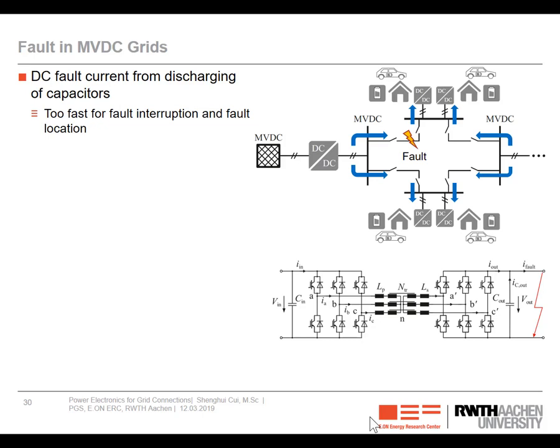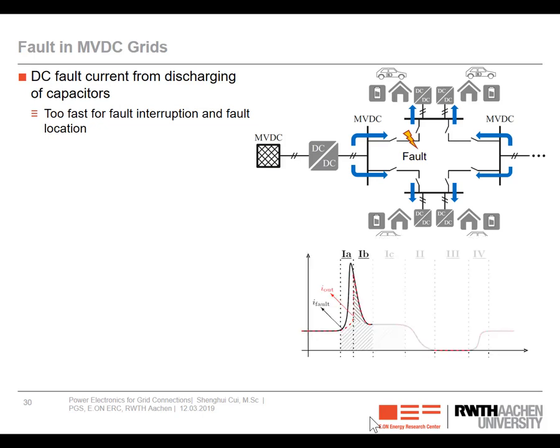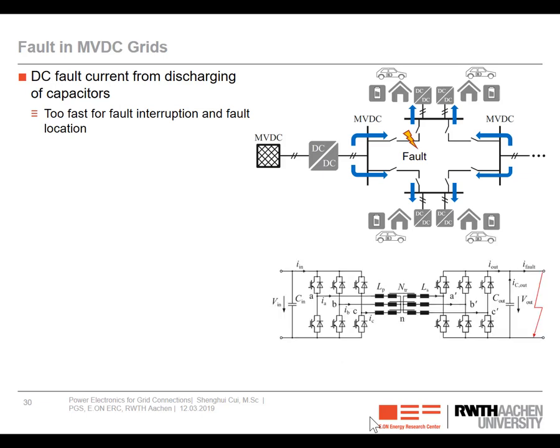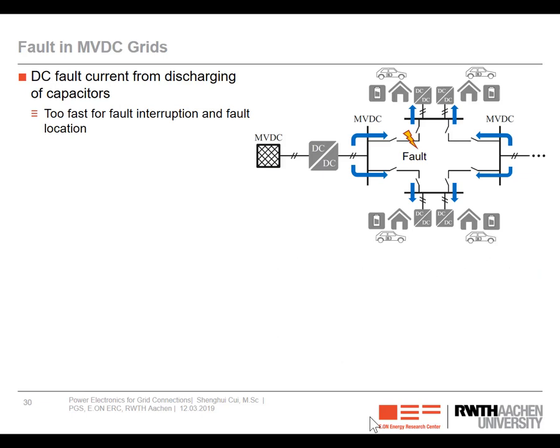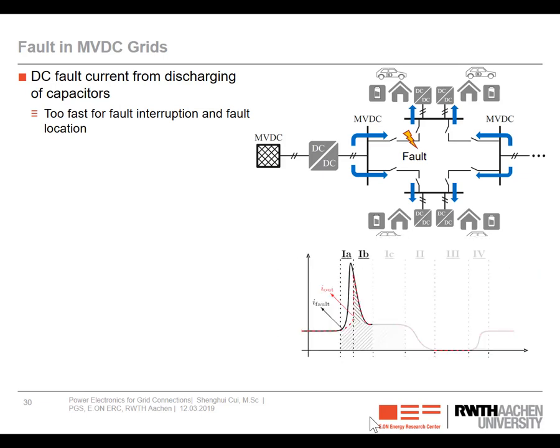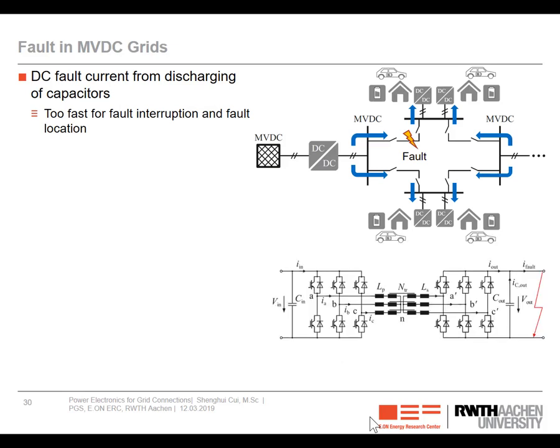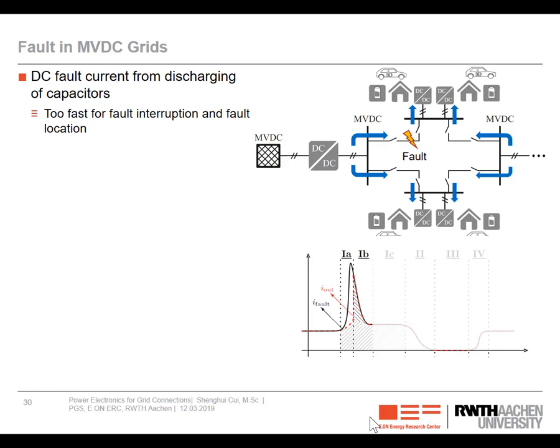And after this, when this capacitor is getting discharged, then we will see a very large overcurrent here. But when this is getting discharged, fortunately, the current flowing through the electronic devices is decoupled from this fault current until this capacitor is fully discharged.